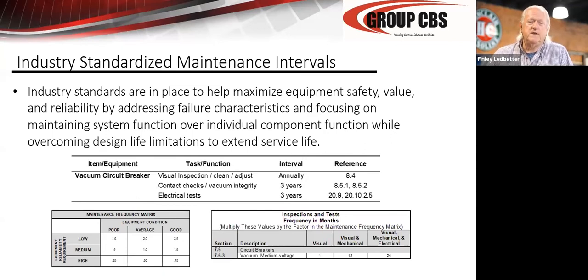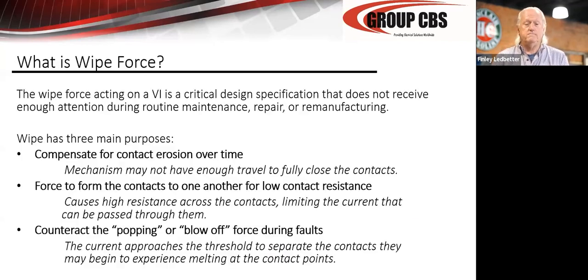NETA has thousands and thousands of years of experience in maintaining electrical equipment. And all of that went into developing these standard maintenance intervals. And it's something you should consider. If you're operating outside of these, let's just say that NETA says you should maintain this equipment every year, a visual inspection, and you're not doing that, you probably need to go back and rethink and justify why you're not using this particular standard, because these are very well thought out.